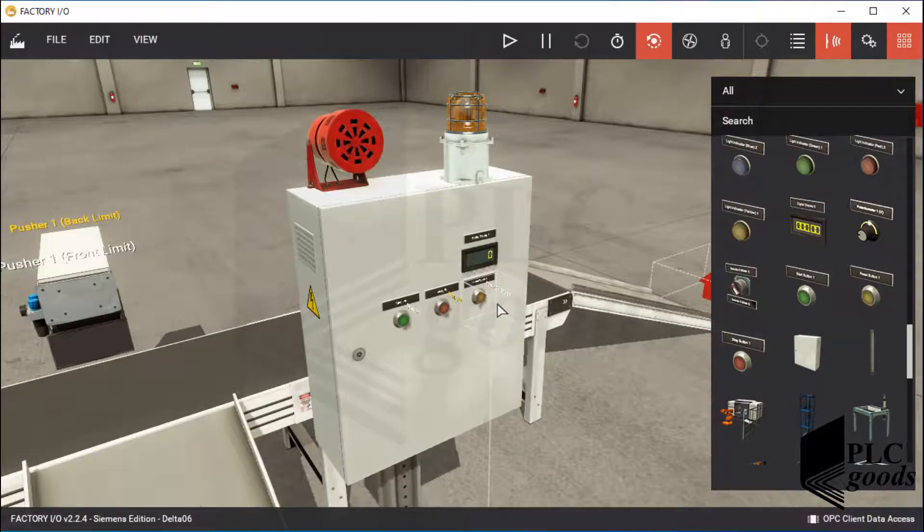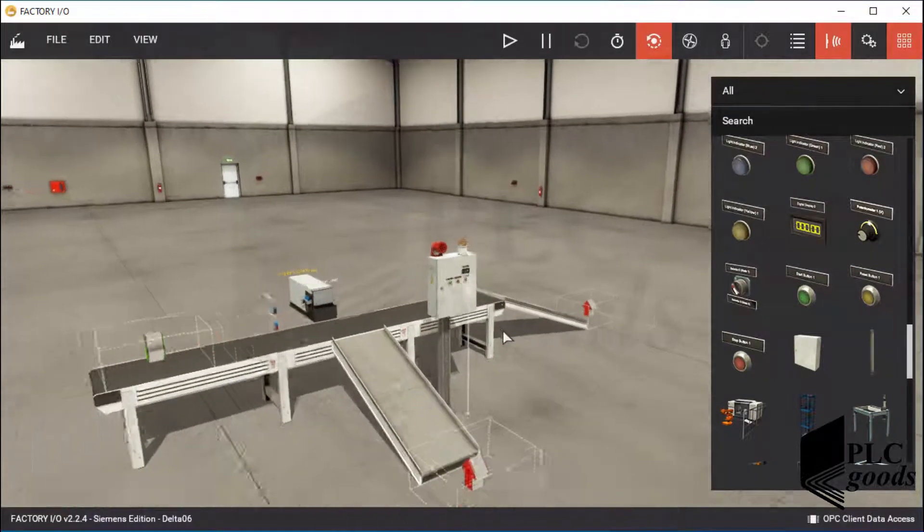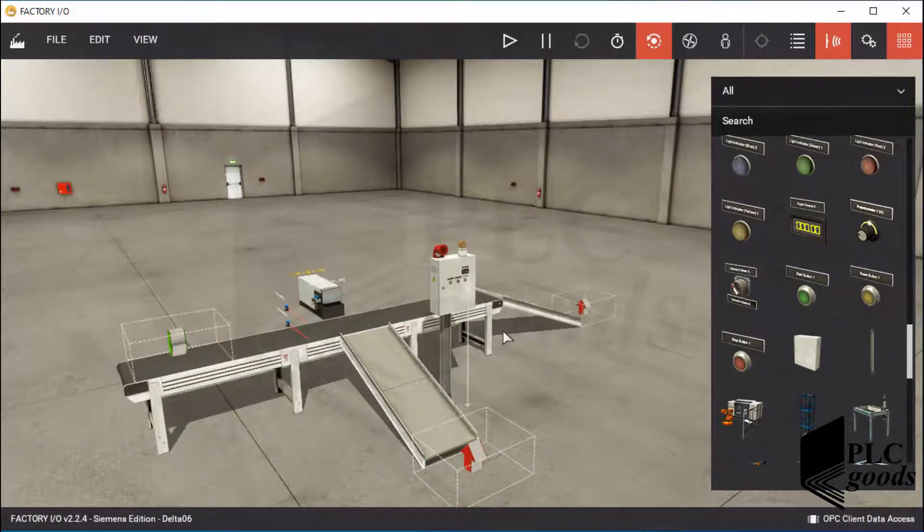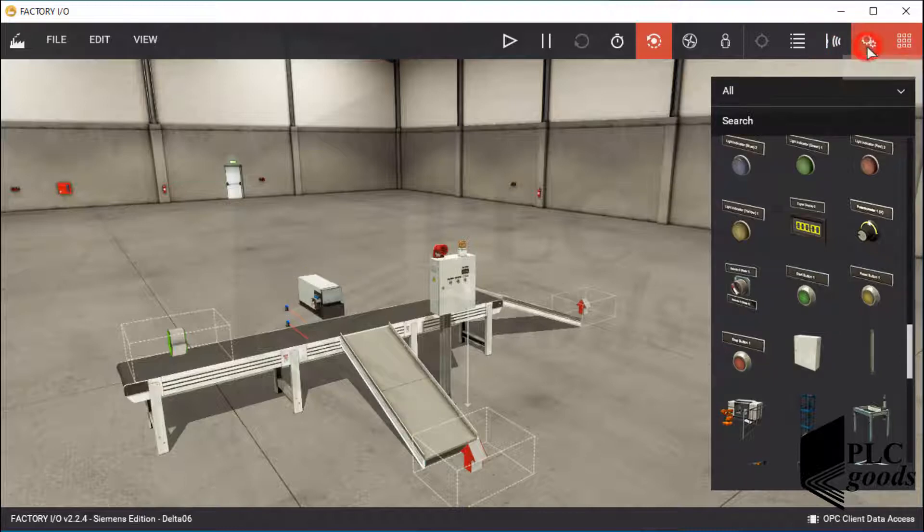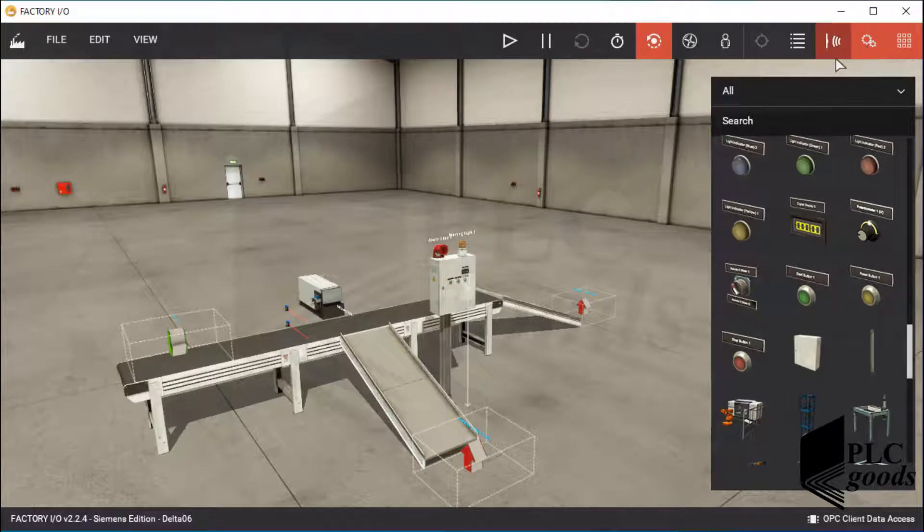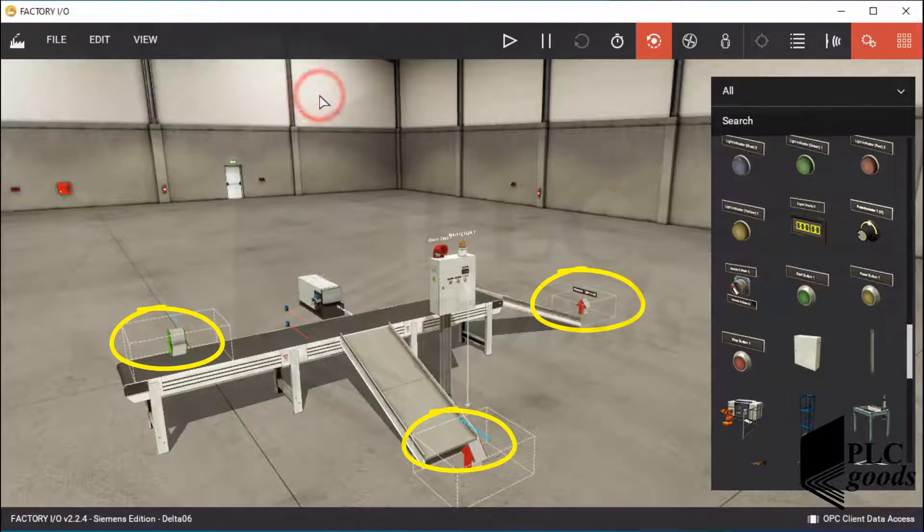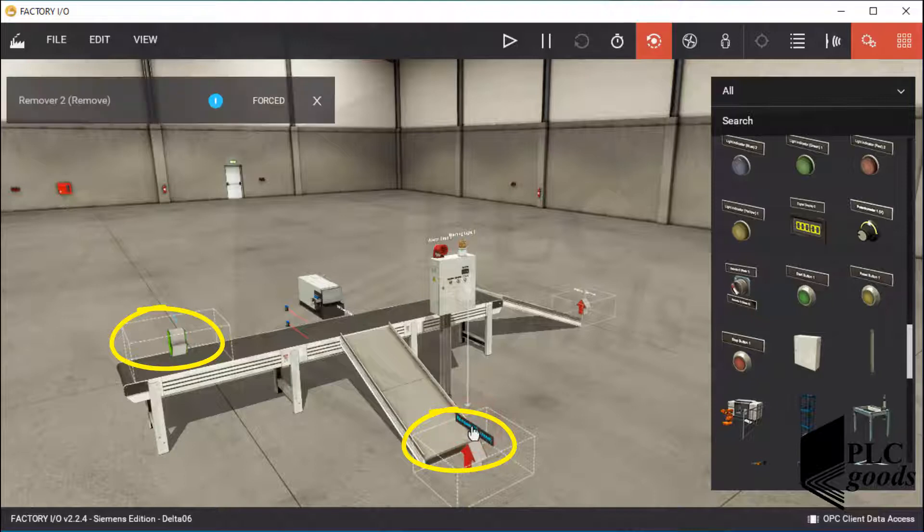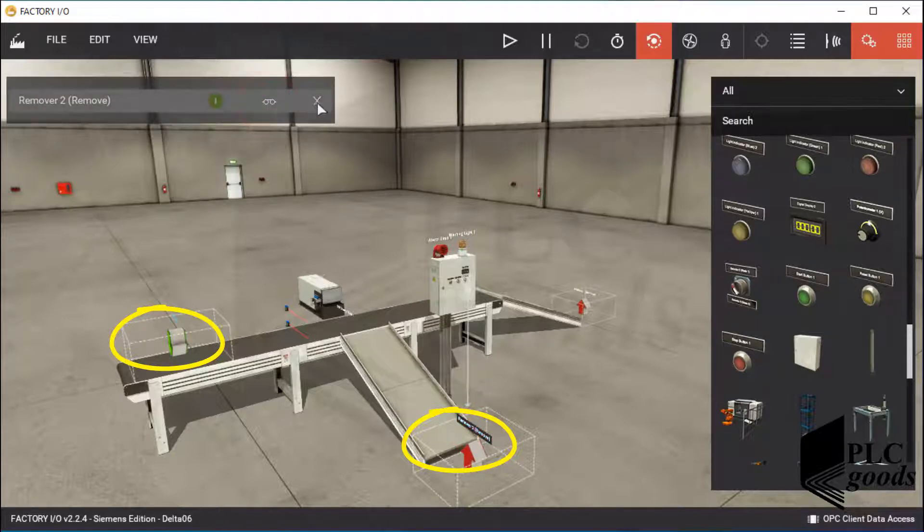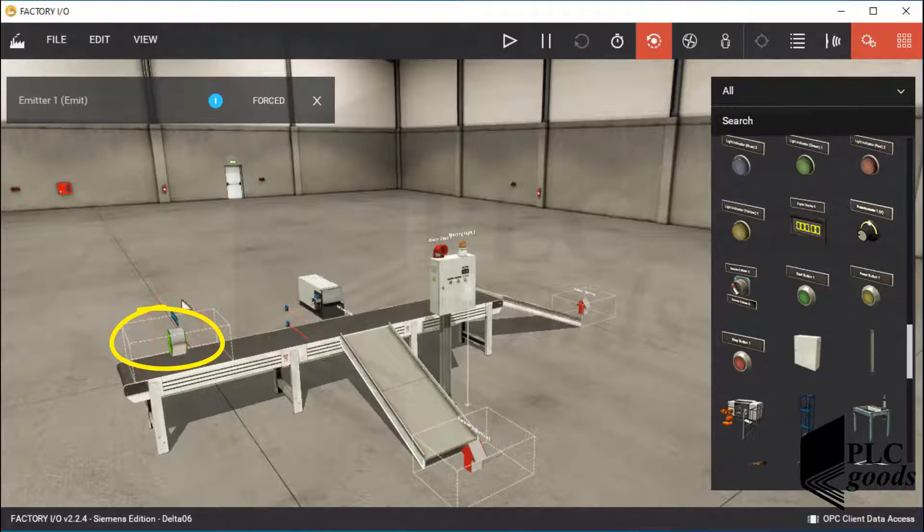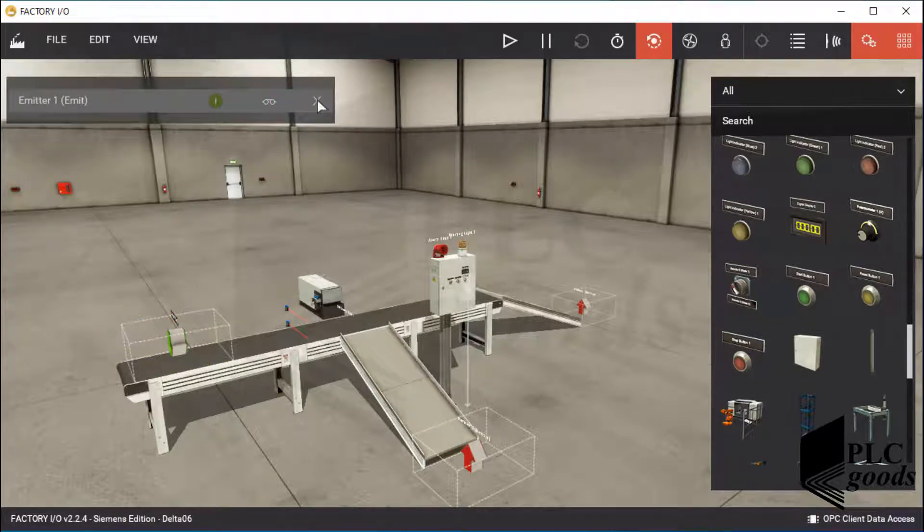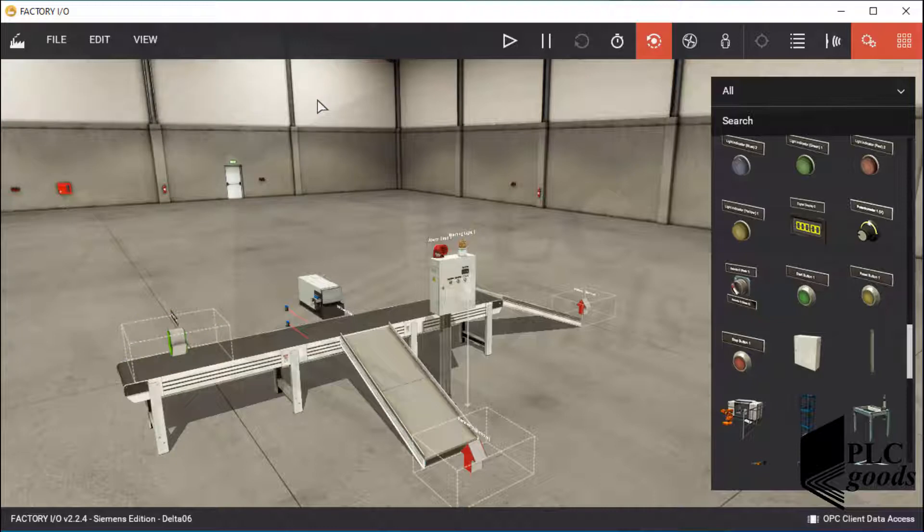Another important point in this project is how a production line must be started or stopped. Usually, a production line starts to turn on devices from the last one and stops them from the first one. By default, inserted removers and emitter are activated. Let me exit them from the force mode, because I want to control them with the PLC program. My program must start removers and belt conveyor, and after 5 seconds, turn on the emitter. For the stop process, first the emitter must be stopped, and after 15 seconds which the belt conveyor has moved all boxes, PLC must stop the belt conveyor and also two removers.